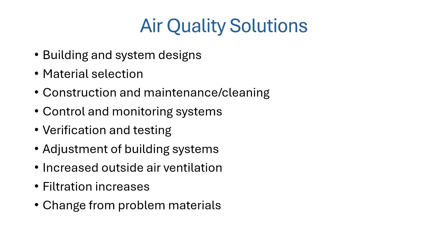On outside ventilation, we did an inspection on a private school a year or so ago that had about 7 or 8 buildings, each 2 or 3 stories, each with rooftop units. We looked at all the rooftop units, and of about a dozen, only 2 had the outside air even open. Walking into these buildings, you could tell. So saving energy is often counterproductive to air quality, and we have to consider that as we operate buildings.